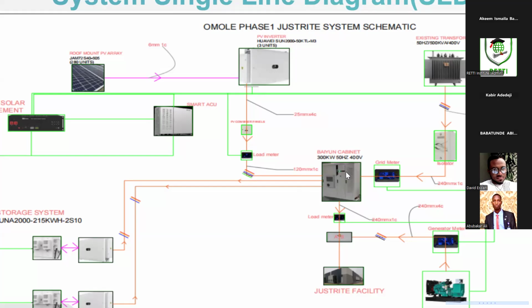If the load is always priority, we take this away from the load — do we have anything left? If yes, go and charge the battery. If not, based on your settings — what is the priority? Is it solar, grid, battery, and gen, or PV, battery, grid, and gen? I would advise, based on what one of the chairmen said, that since you've already bought the battery, there's no point letting the grid come before the battery. So in the ranking it becomes PV, battery, grid, and generator.